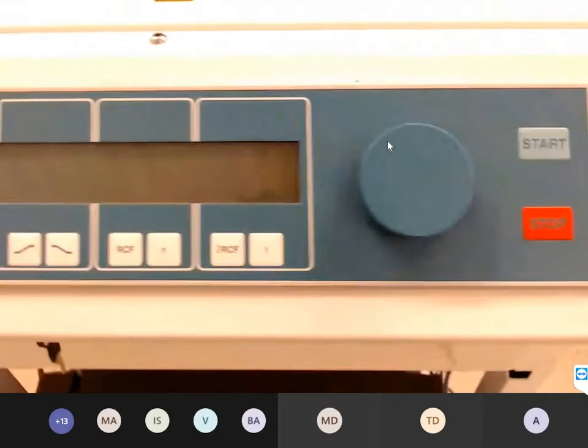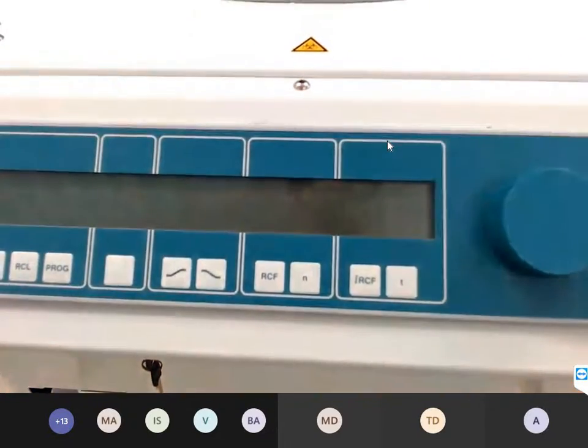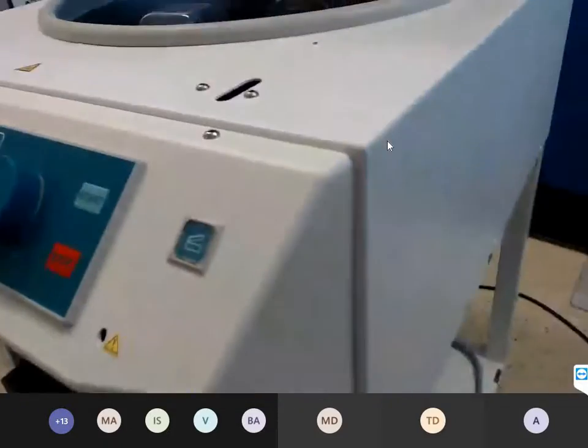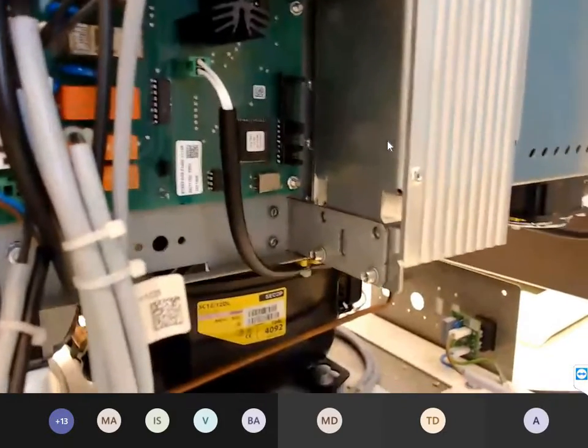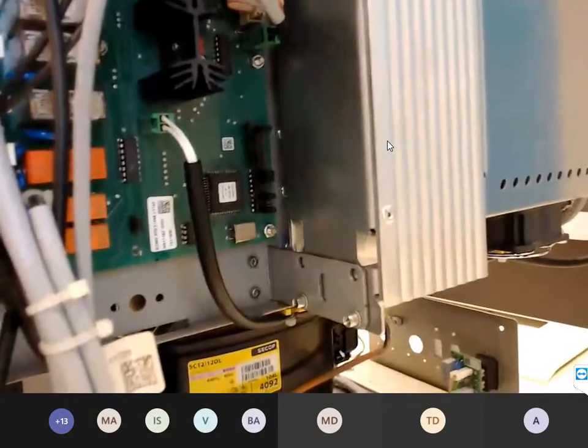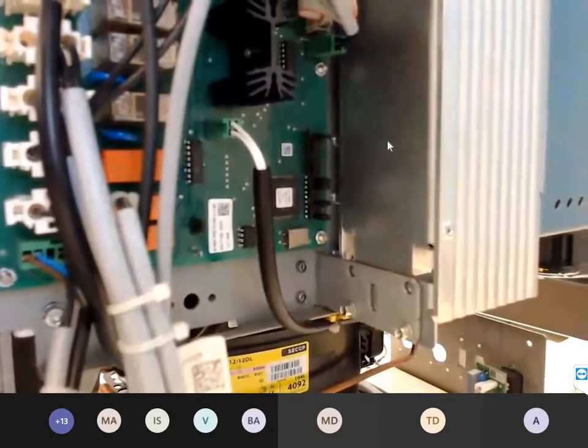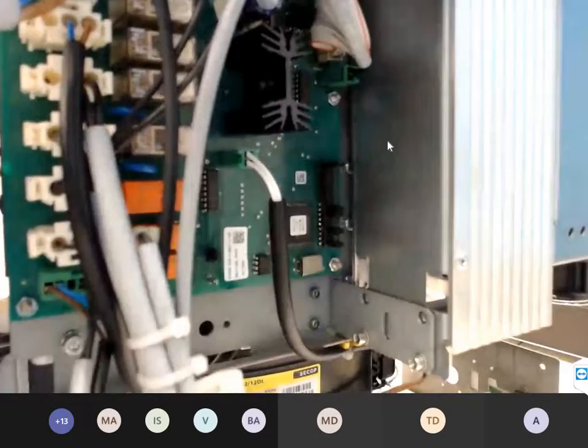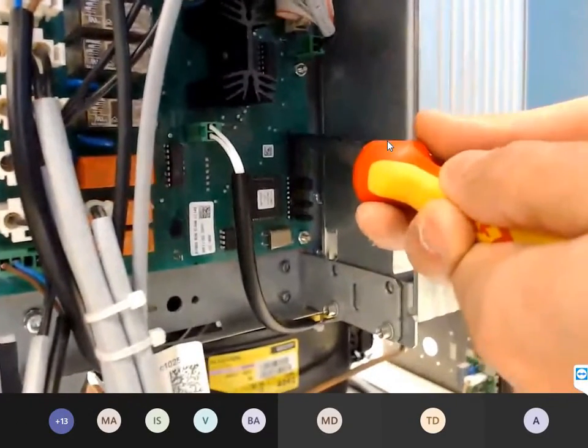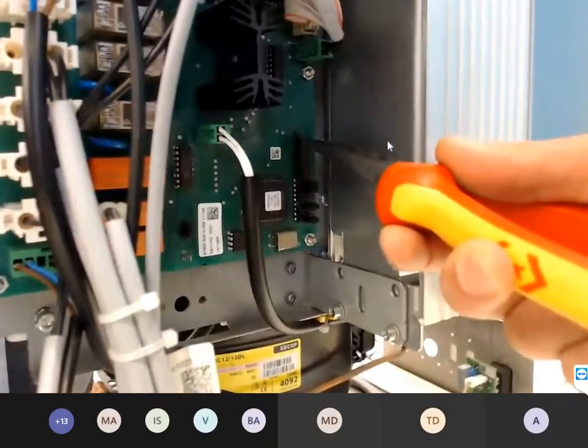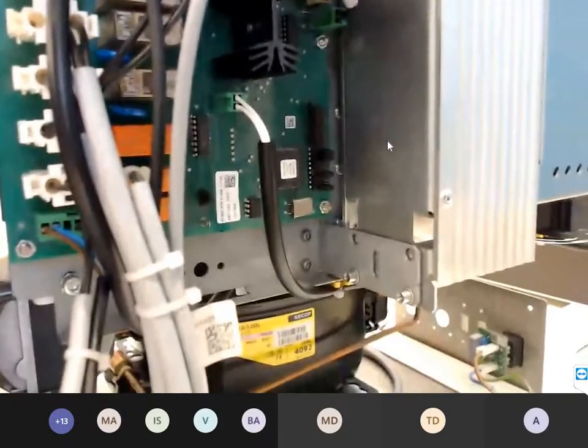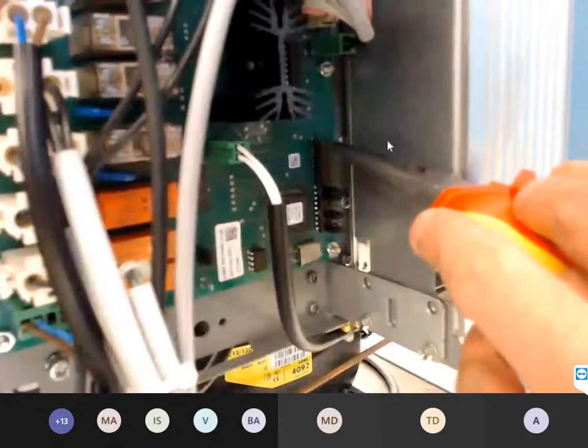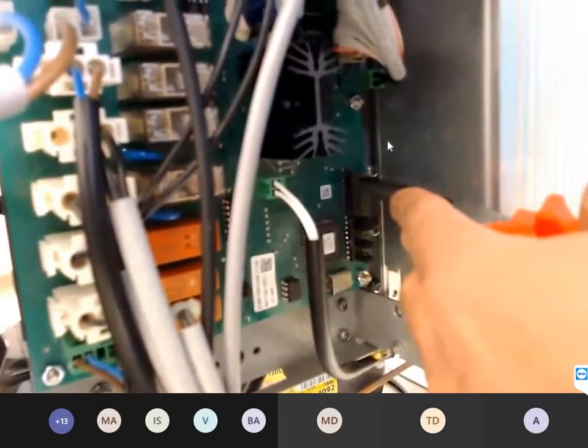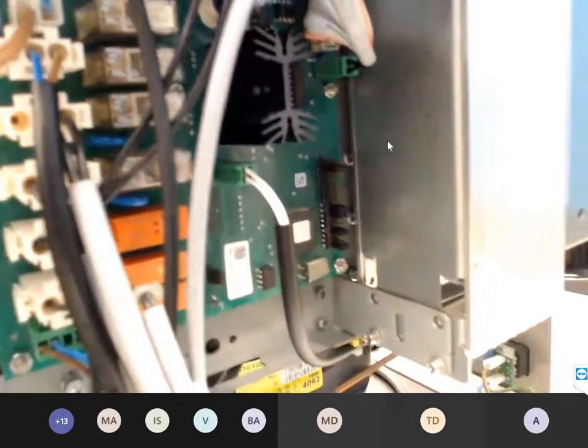And the second important setting is initialization. You have to make an initialization in case of a replacement of the control board, frequency converter, or the electronic board. Very important. That's the first step. For this, change the jumper position to B1. You also find the positions in the service manual. B1, switch on the device again.